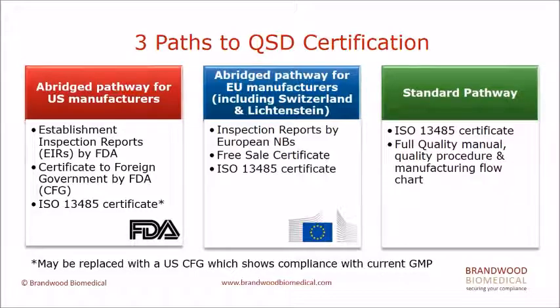And there is a standard pathway for ISO, need to provide ISO 13485 certificate and a full quality manual, quality procedure, manufacturing flow chart. So in summary, if the manufacturing facility is in US or Europe, are eligible to register through the simplified pathway by providing either the EIR, the Establishment Inspection Report, or the notified body report from the 11 notified bodies to waive the full quality system documents. However, the reviewing timeline are the same for all pathways.